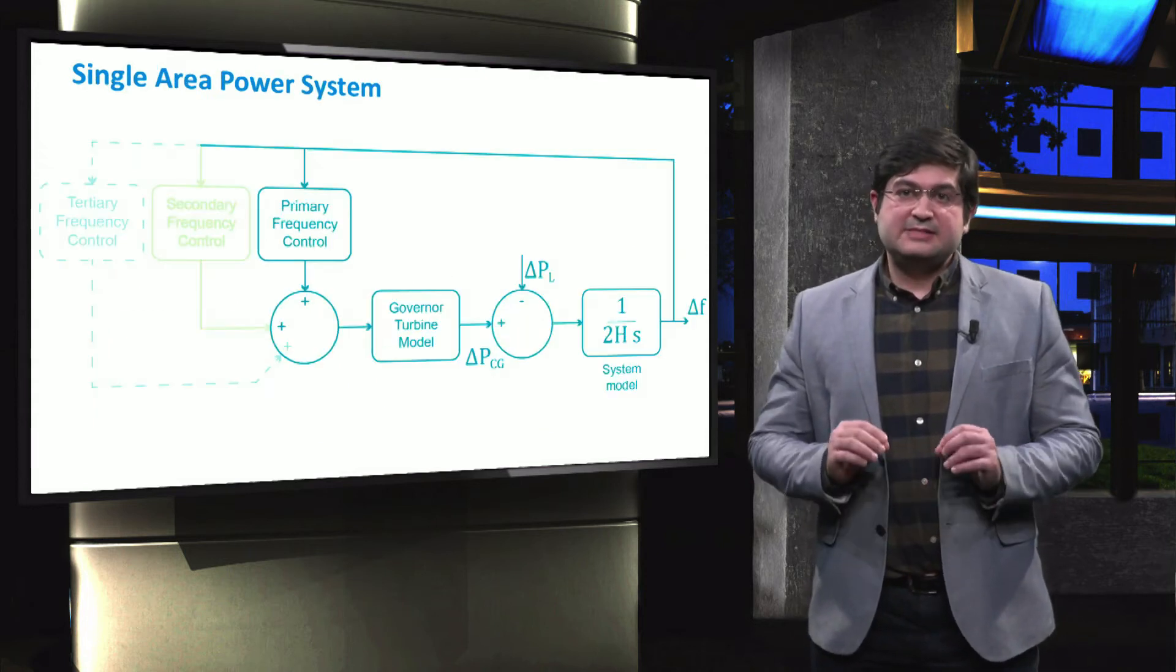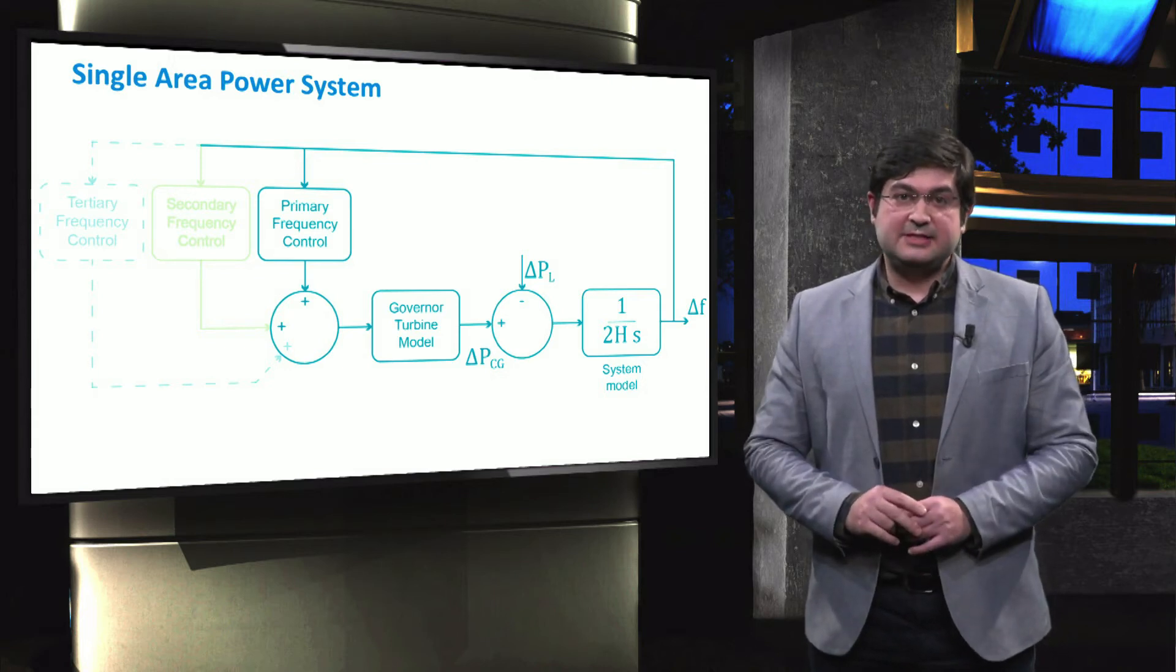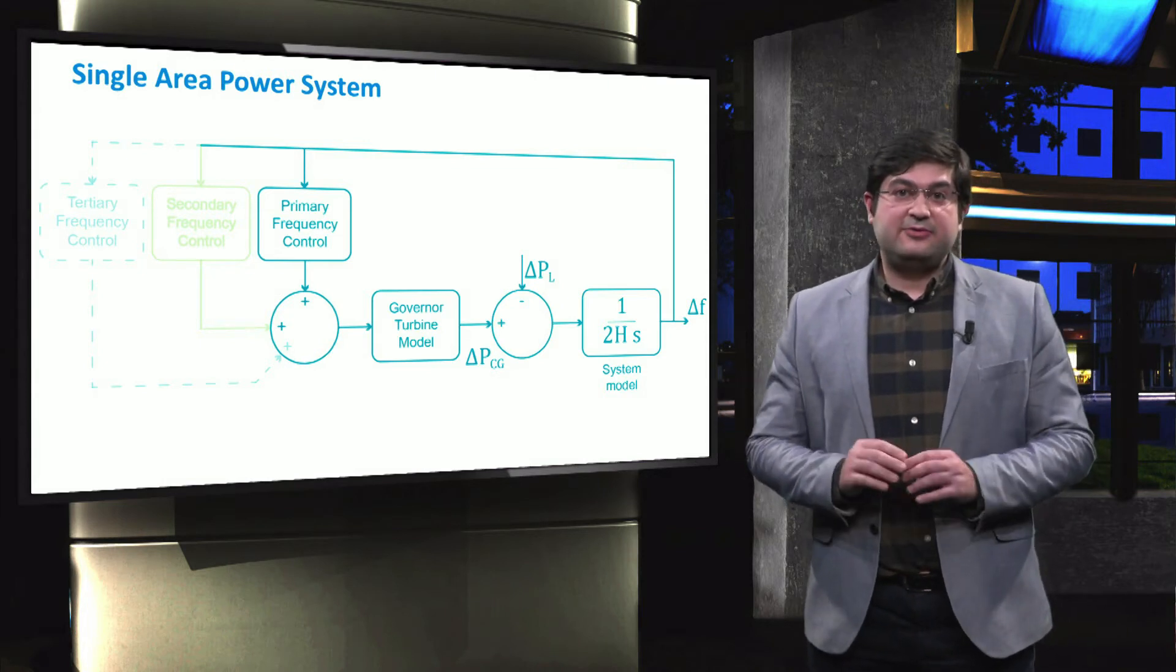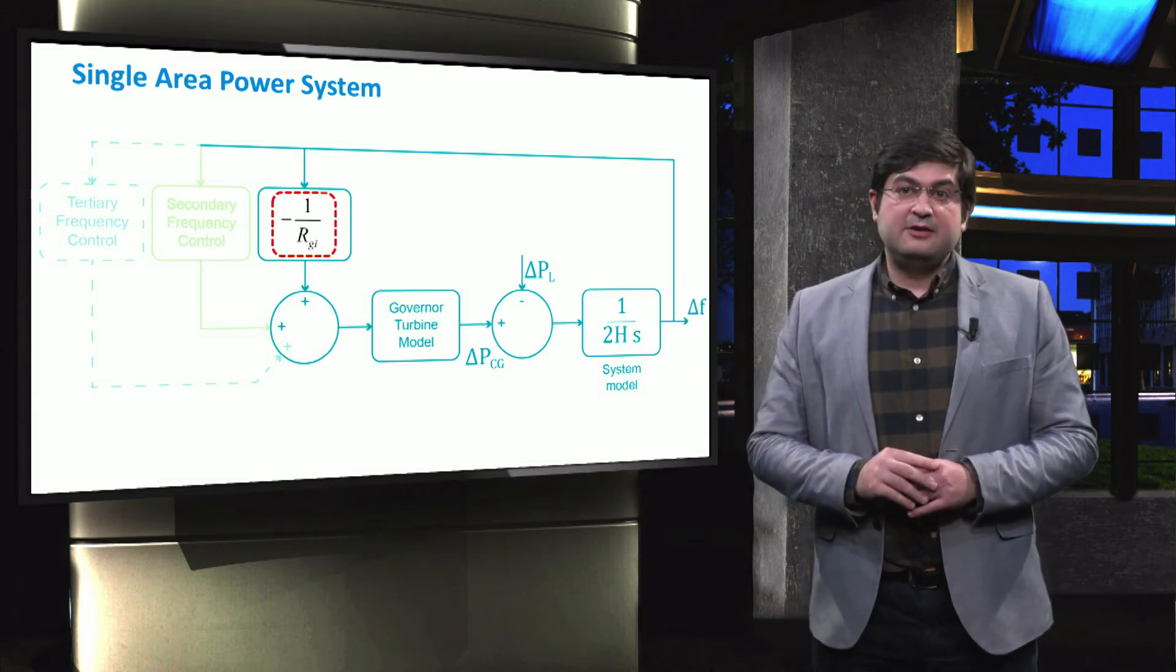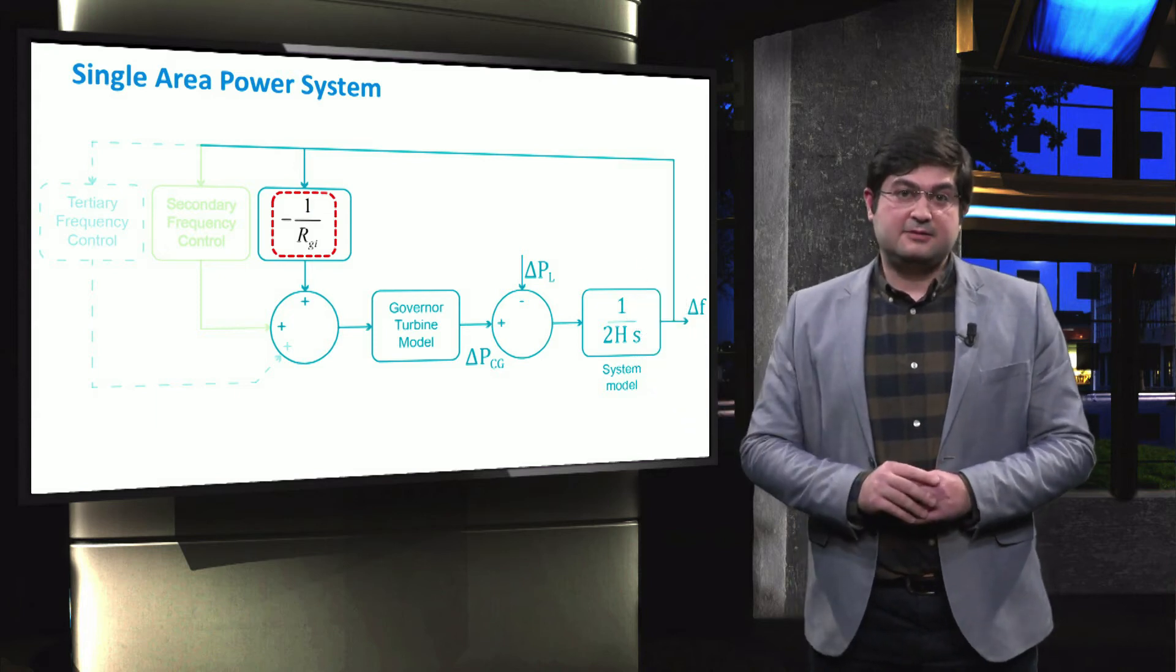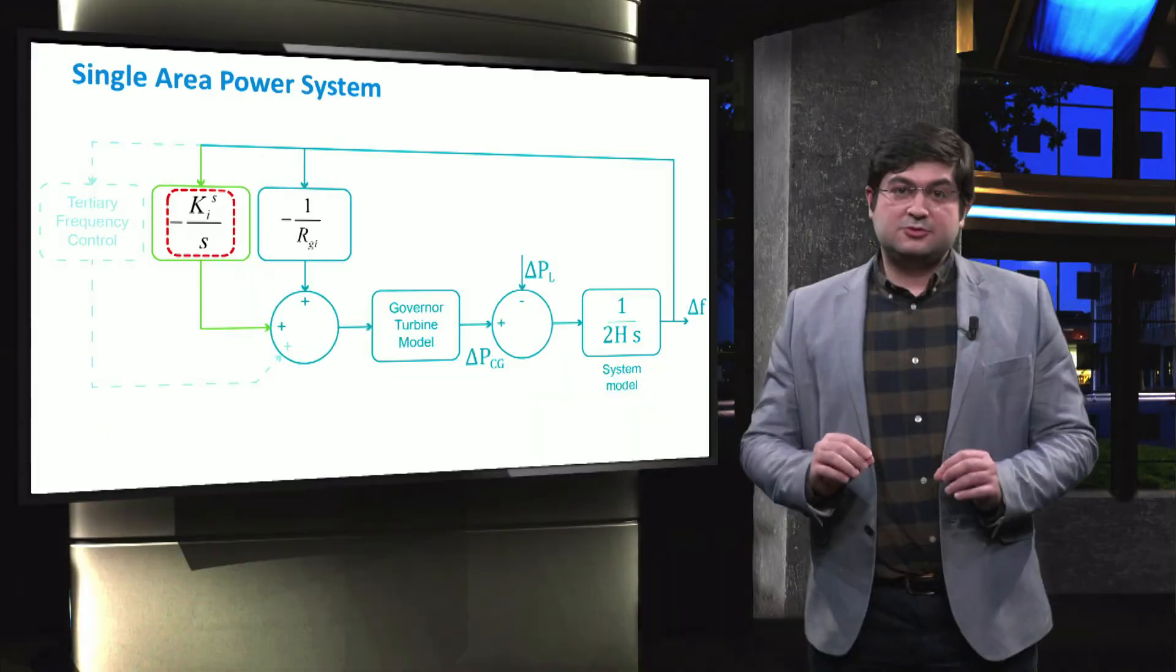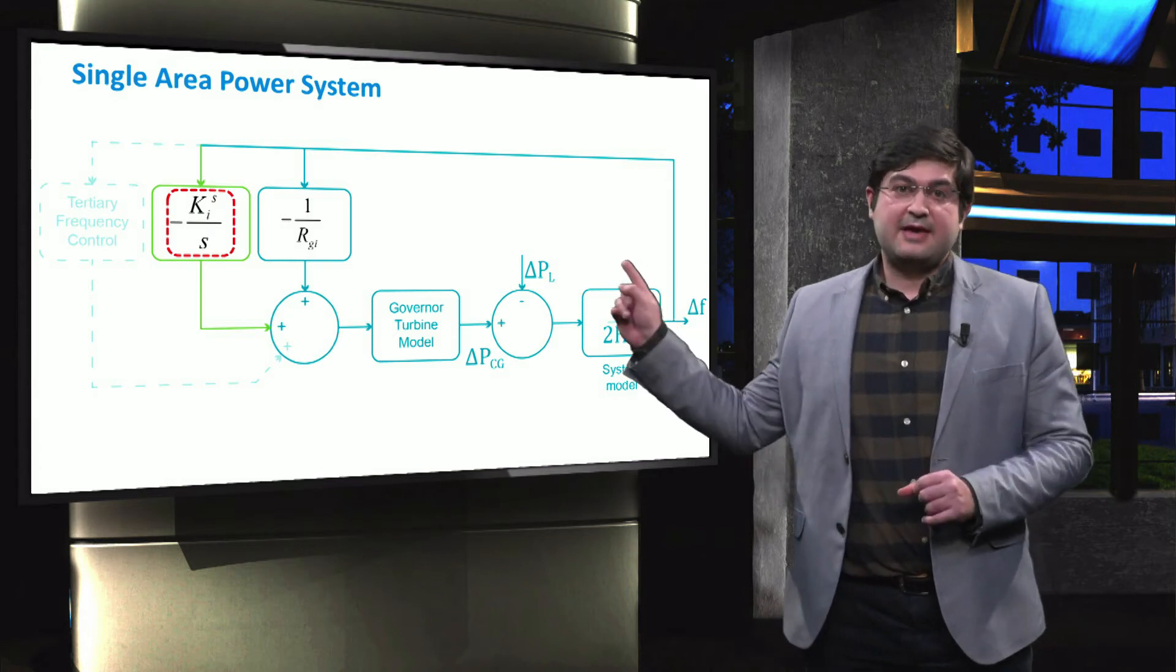In the slide, we see the generic frequency control scheme of single area power system, where the mismatch between the generation and the demand is reflected as the frequency deviation delta-f. To implement the primary control, we mentioned that the inverse of the droop control, Rgi, is multiplied. Now we show how the secondary control can be implemented in one generating unit to remove the steady state error of the frequency. To do so, it is required to apply an integral controller with a coefficient Ki.